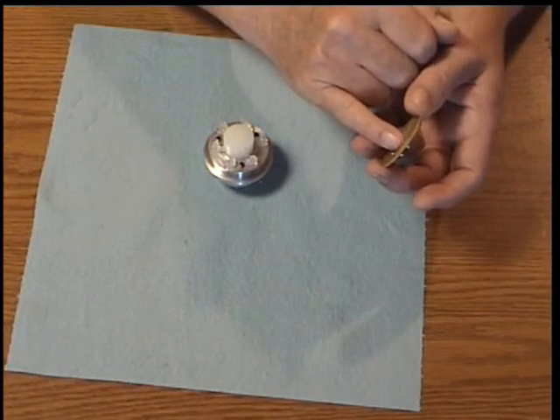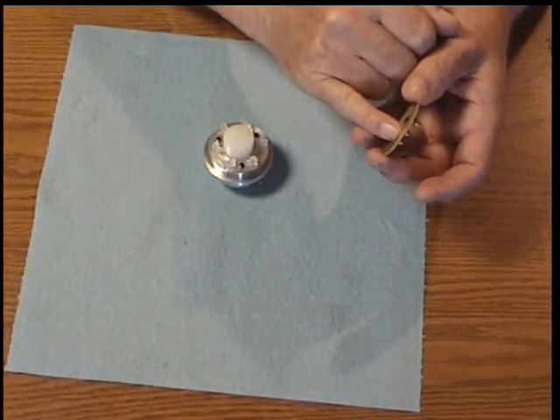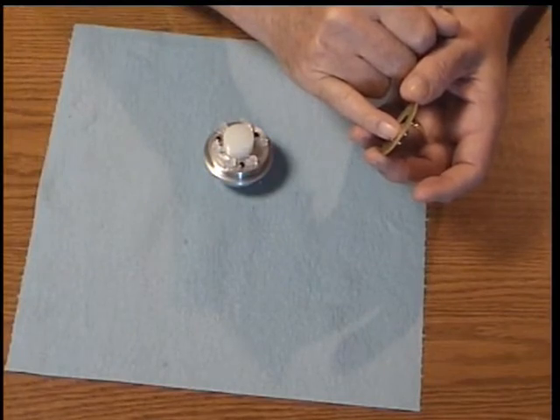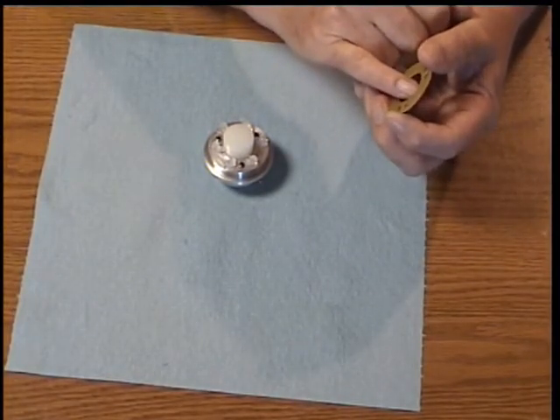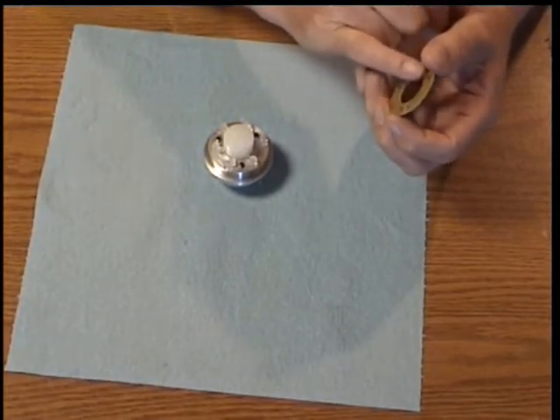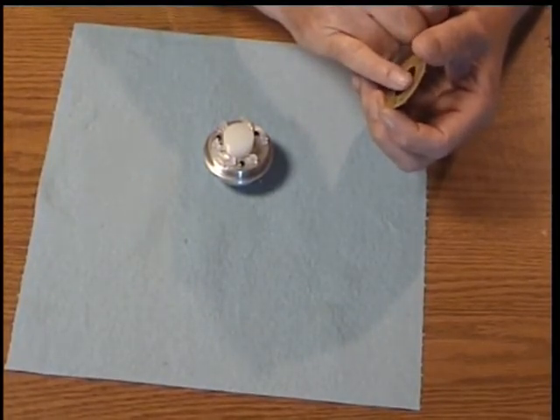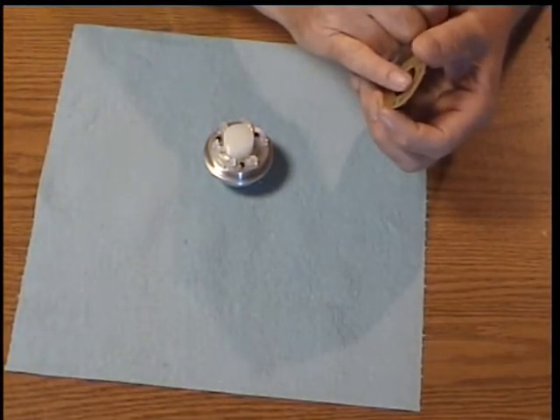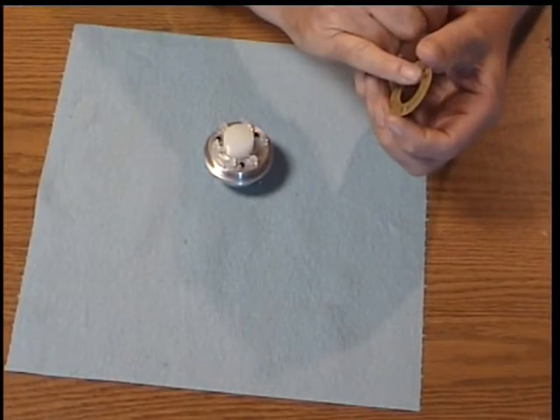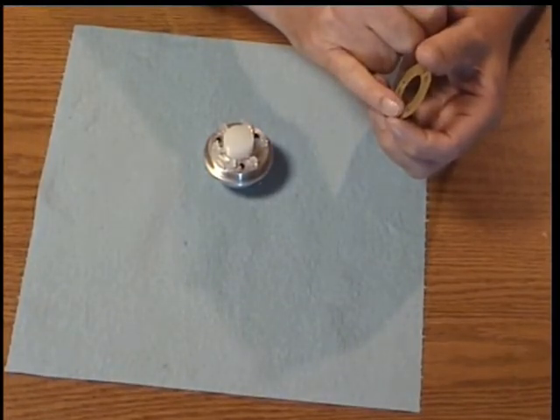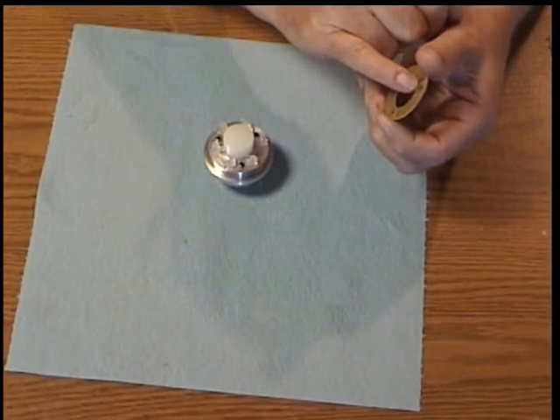By the way, the reason that we put the set screw here between the two balls is so that when you are making adjustments later on, you are making the maximum adjustment for the motion of the set screw, the movement of the set screw. If we were to put the set screw here in this broader area between the pairs of balls, what would happen is that the printed circuit board might have a tendency to bow such that there would be flex at the screws and reduce the accuracy of the econoprobe. So, again, we want the set screw to be on the land between the balls.